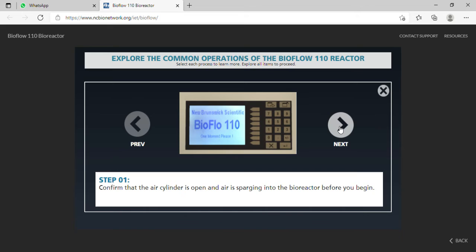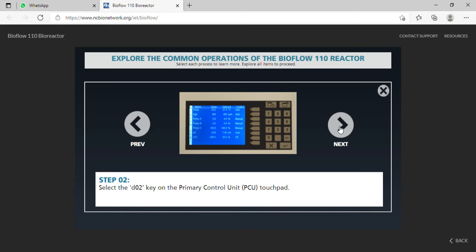Step 1. Confirm that the air cylinder is open and air is sparging into the bioreactor before you begin. Step 2. Select the DO2 key on the primary control unit PCU touchpad. Step 3. Select Calibrate on the PCU. This will take you to the Calibrate menu. Step 4. Select Set 0 on the PCU touchpad to begin the calibration process. Step 5. Enter the number 0 on the PCU touchpad.